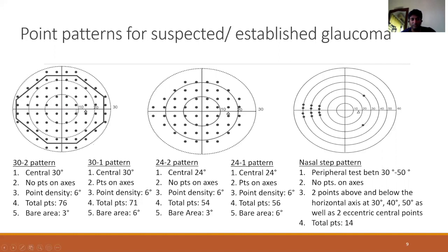The 24-2 is a subset of the 30-2 where the outer set of points have been excluded except for two nasal points. It has no points on the central axis; total points covered are 54, point density is 6 degrees, and the central bare area is 3 degrees. The nasal step pattern is used only for detection of very early nasal step defects seen in glaucoma. The area tested is between the peripheral 30 and 50 degrees, with two points above and below each meridian, and two isolated points under 30 degrees in the nasal area.